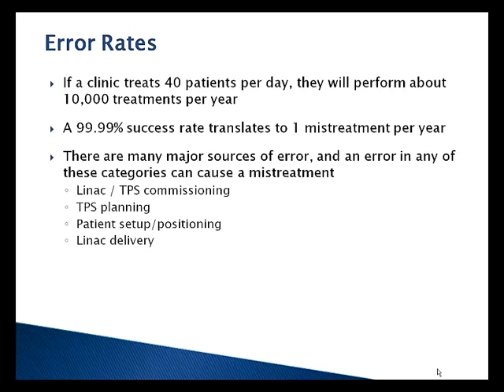Let's say your clinic treats about 40 patients a day, either one heavily loaded machine or a couple lighter loaded machines. You're going to treat about 10,000 fractions per year. If you do that with a 99.99% success rate, that means every year you're going to mistreat one patient. And 99.99% is really high, and it sounds nice, but we also have to make sure that every system, the Linac and planning system, has been commissioned. The planning was done correctly, patient setup and positioning was done correctly, and the delivery was done correctly. All of these have to be working together to not mistreat a patient.